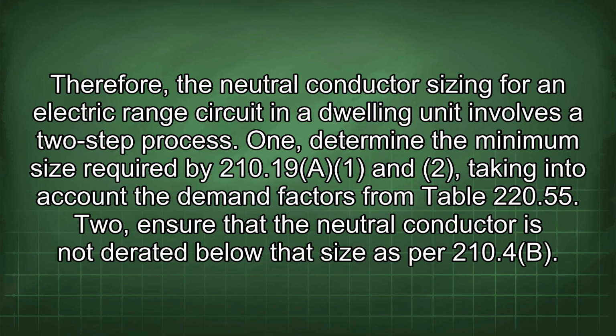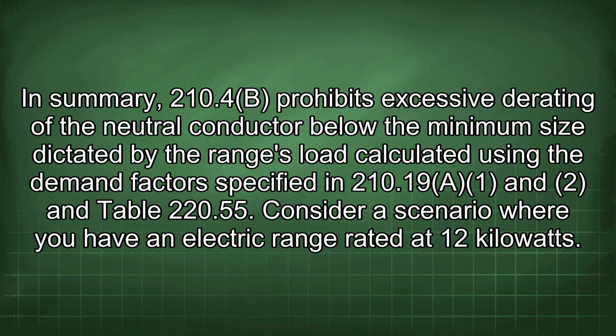Therefore, the neutral conductor sizing for an electric range circuit in a dwelling unit involves a two-step process. 1. Determine the minimum size required by 210.19(A)(1) and (2). Taking into account the demand factors from Table 220.55. 2. Ensure that the neutral conductor is not derated below that size as per 210.4b. In summary, 210.4b prohibits excessive derating of the neutral conductor below the minimum size dictated by the range's load calculated using the demand factors specified in 210.19(A)(1) and (2) and Table 220.55.